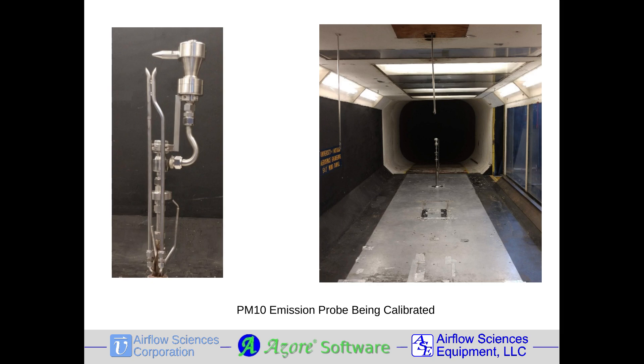Very fine PM is measured using the EPA test protocol of Method 201A, which focuses on PM in the size range below 10 microns, called PM10, and below 2.5 microns, or PM2.5. These measurement methods use a probe head that is a combination of an S-type pitot probe for velocity and a vacuum-assisted sampling nozzle with a cyclone separator for the particulate.